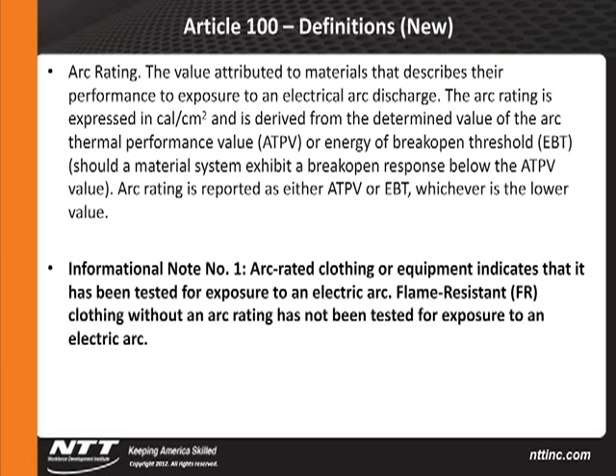Now, as I said, one of the things that changed out there is some definitions, and this is a significant change. Arc rating. This is dealing with clothing. The value attributed to materials that describe their performance to exposure to electrical arc discharge. The arc rating is expressed in calorie centimeters squared and is derived from the determined value of the arc thermal protection value. Folks, simply this. Today, for clothing to be used for this protection, it has to have a label in it that says ATPV, arc thermal protection value. Just saying FR is not good enough. If it says FR, there still has to be a label in it to identify it that it meets that requirement. And that arc rating has to be equal to or greater than the hazard they're facing.